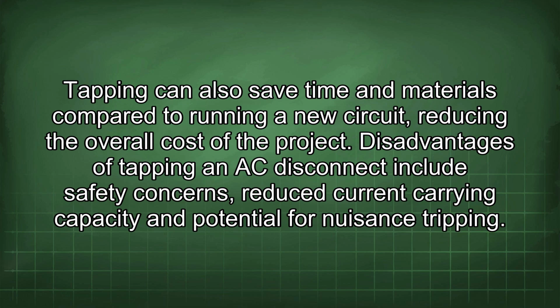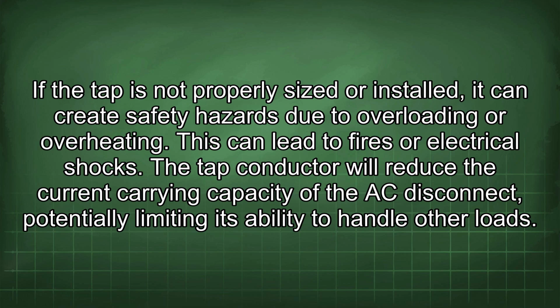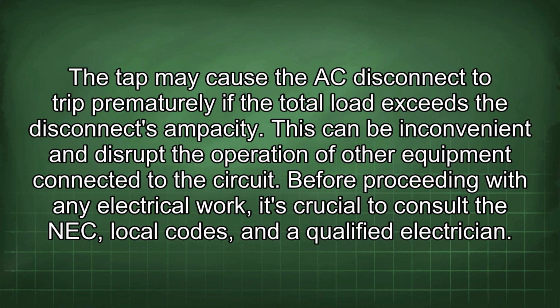Disadvantages of tapping an AC disconnect include safety concerns, reduced current carrying capacity, and potential for nuisance tripping. If the tap is not properly sized or installed, it can create safety hazards due to overloading or overheating. This can lead to fires or electrical shocks. The tap conductor will reduce the current carrying capacity of the AC disconnect, potentially limiting its ability to handle other loads. The tap may cause the AC disconnect to trip prematurely if the total load exceeds the disconnect's ampacity. This can be inconvenient and disrupt the operation of other equipment connected to the circuit.